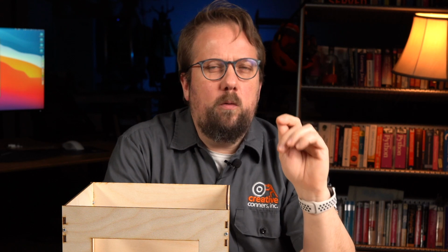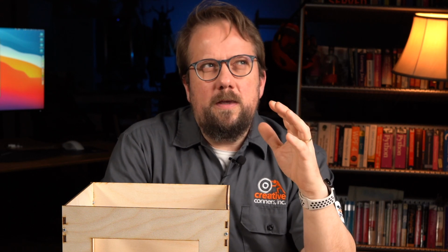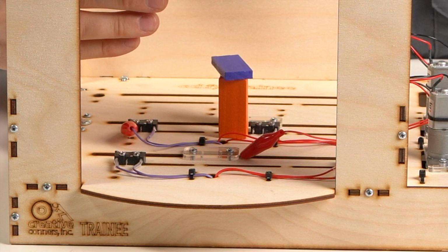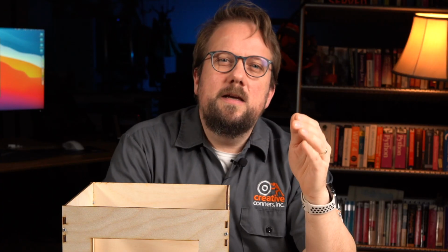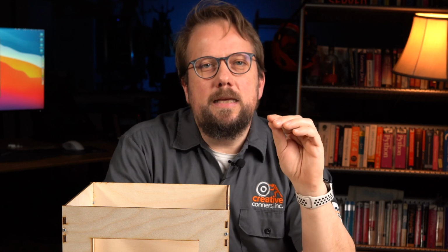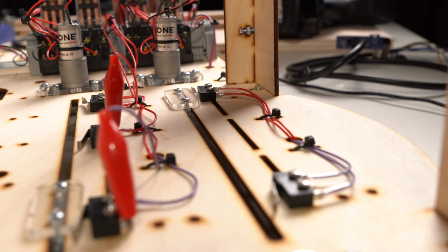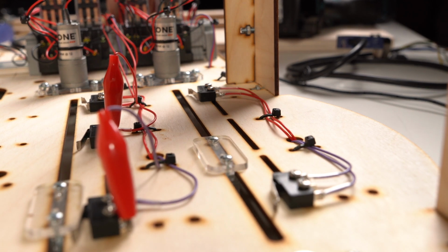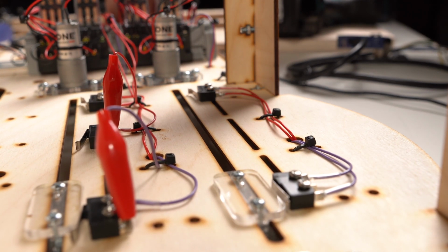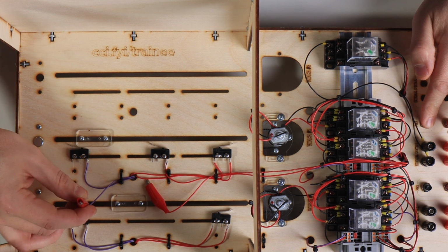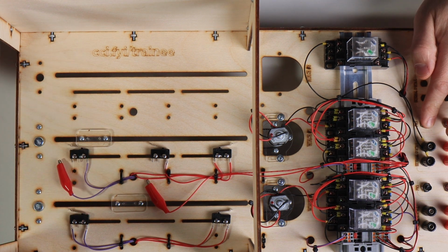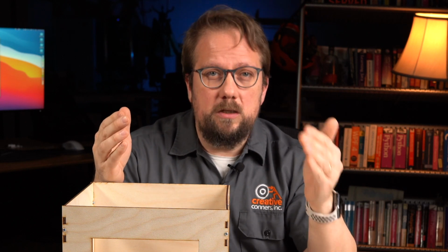The difference in logic here is subtle but important. Rather than designing it so it says, send a signal when to stop, it's send a signal as long as it is safe to move. If the signal is interrupted for any reason, either because you've actually hit the limit switch or because the connection to the limit switch has broken, the motor stops. It fails to a safe condition.